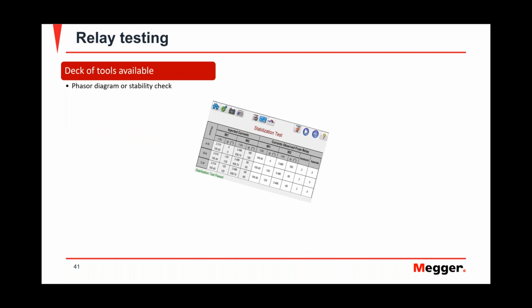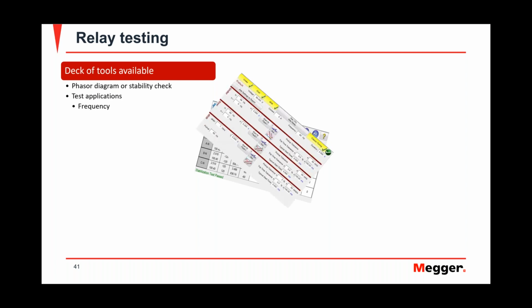So there are different tools provided in relay testing software that will help you with all this. One tool is the stabilization test. This is like a metering check. Before you go in, you have to confirm that your wiring from your relay is tested: whatever you want to inject, the relay is receiving it. That's one of the first things you should do, making sure that your wiring is correct and that your settings are correct. They call it a stabilization or a metering check, to make sure that your voltages and your currents are being wired to the right place and with the right polarities.